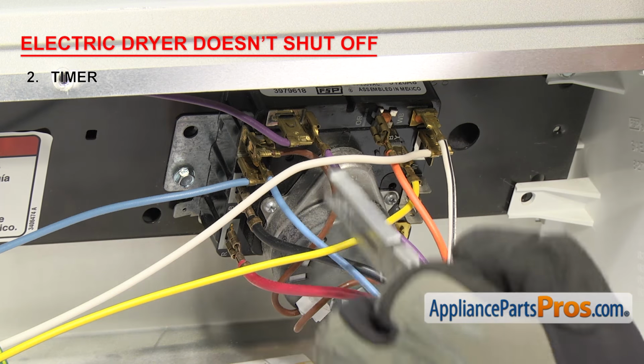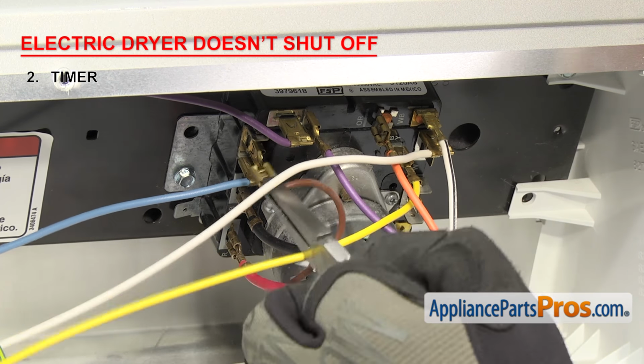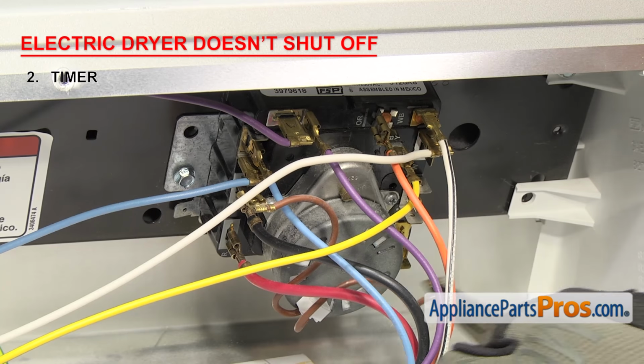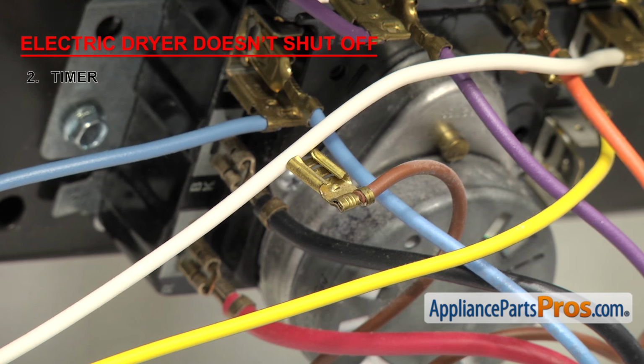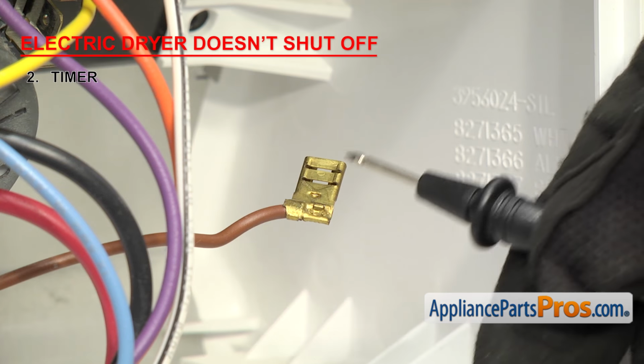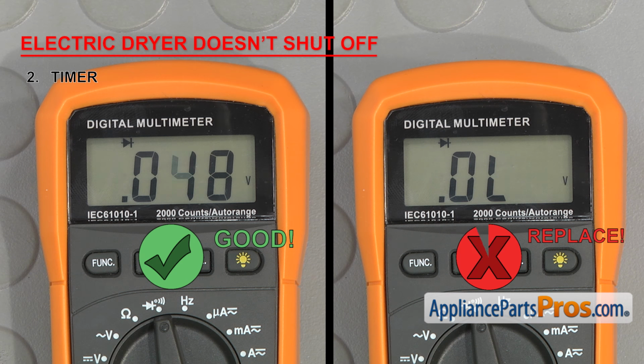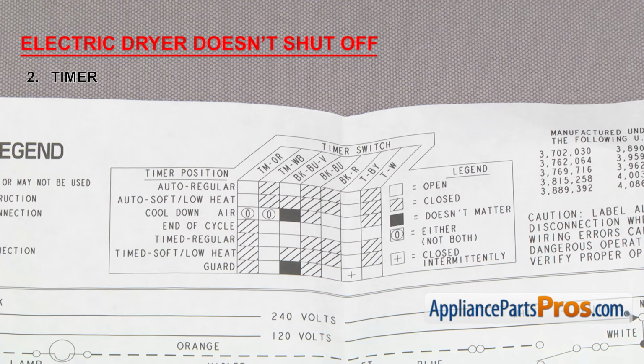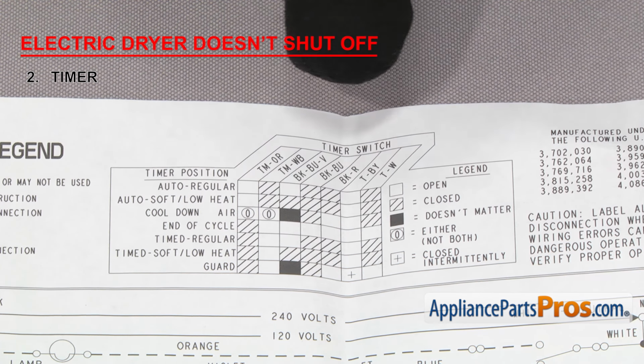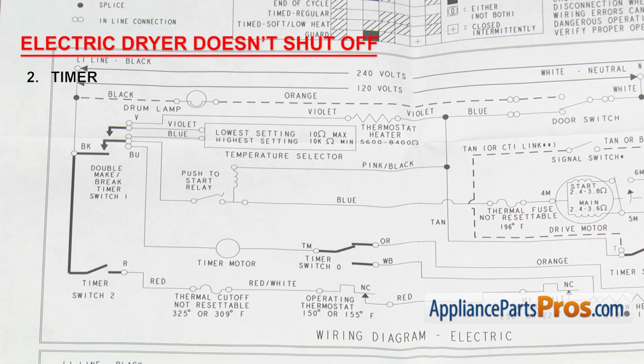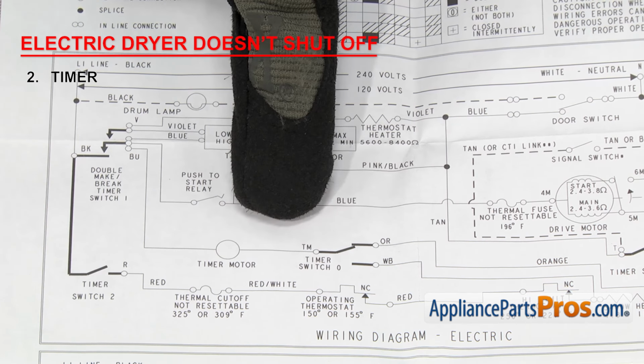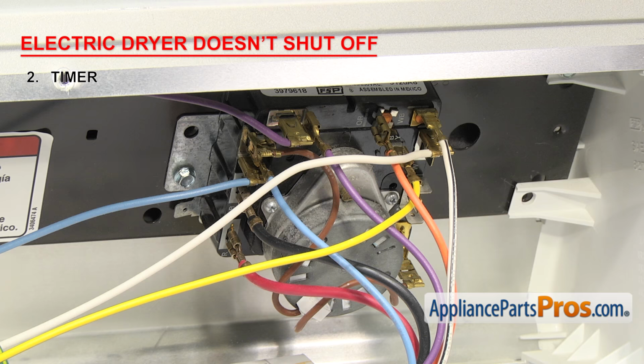To see if the motor has failed, unplug the wires and touch a probe to each one. If you get a reading, the motor is fine, and you can check the timer itself. Because there are so many different timers out there, and the terminals can vary greatly, you'll have to consult your wiring diagram to see which terminals to test in order to see if the contacts inside have failed. If any part of the timer is bad, you'll need to replace it.